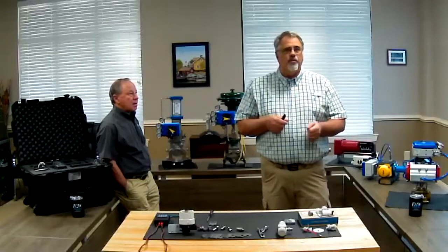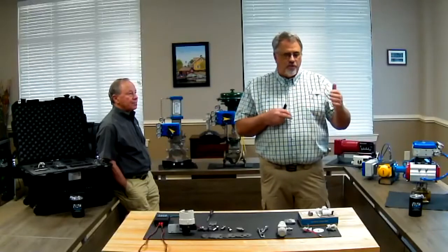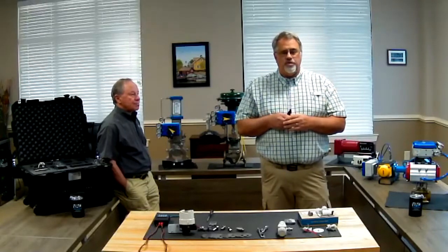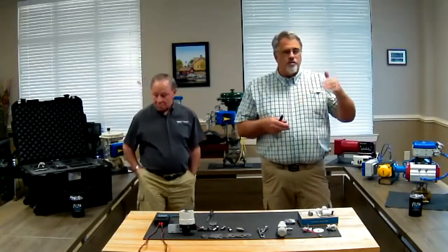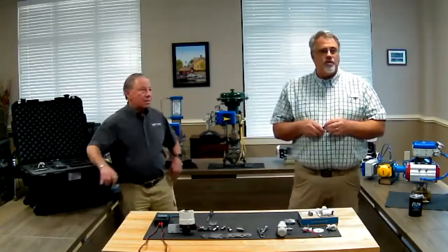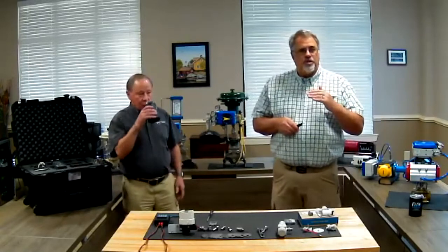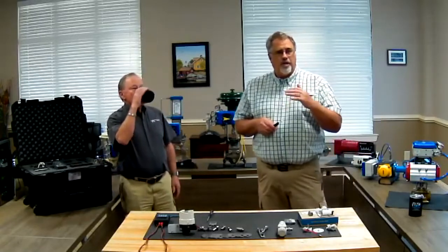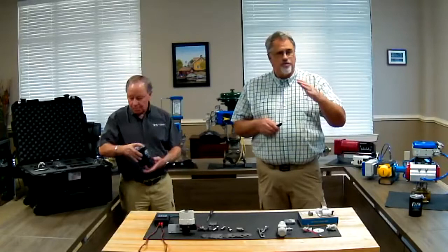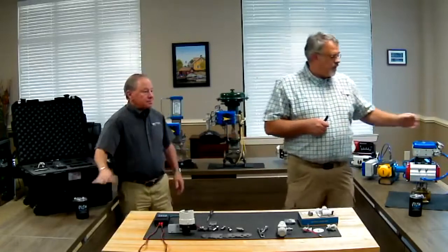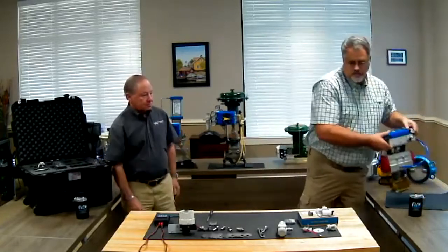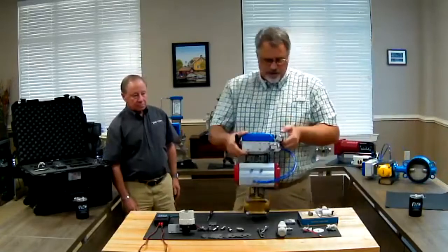They bring in assemblies and demonstrate the complete brand that you as a distributor are selling: your valve, your actuator, the positioner, and how it works. So we're going to take the positioner portion of this one by one. We're going to talk about calibration, modularity, accuracy, troubleshooting, linearity, and so on. And I'm going to do that with this particular valve assembly I have right here.